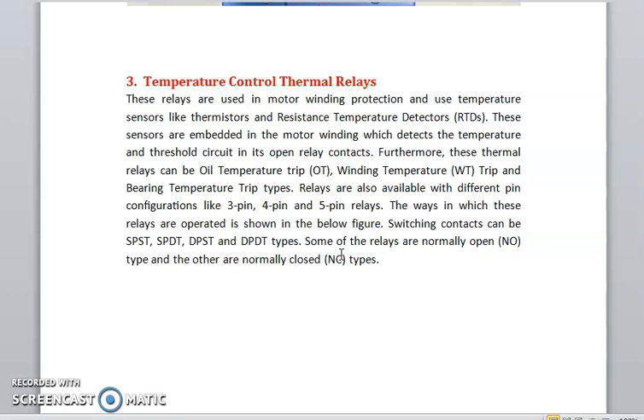Temperature control thermal relays. These relays are used in motor winding protection and use temperature sensors like thermistors and resistance temperature detectors. These sensors are embedded in the motor winding, which detects the temperature and short circuits or opens the relay contact. Furthermore, these thermal relays can be oil temperature trip, winding temperature trip, and bearing temperature trip types.